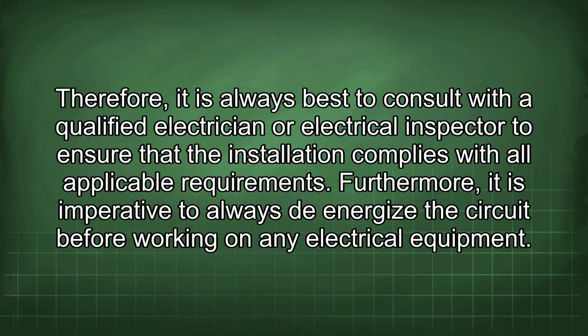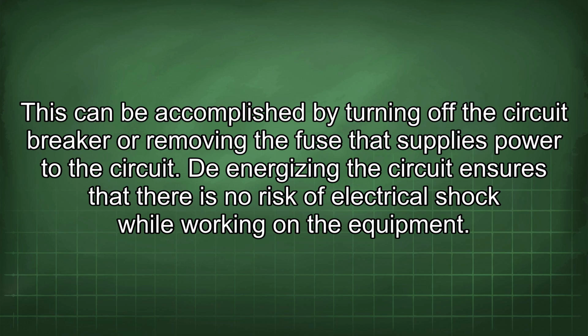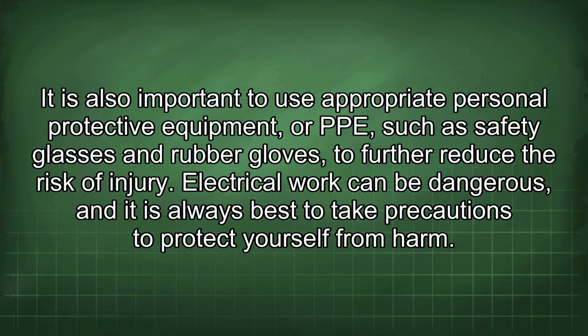with all applicable requirements. Furthermore, it is imperative to always de-energize the circuit before working on any electrical equipment. This can be accomplished by turning off the circuit breaker or removing the fuse that supplies power to the circuit. De-energizing the circuit ensures that there is no risk of electrical shock while working on the equipment. It is also important to use appropriate personal protective equipment, or PPE, such as safety glasses and rubber gloves, to further reduce the risk of injury. Electrical work can be dangerous, and it is always best to take precautions to protect yourself from harm.